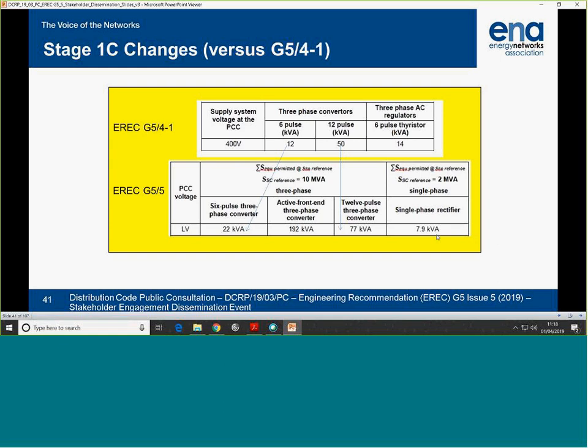And the new figures are from using a revised emission profile, different summation exponents and planning level, all these aspects. And THD is included as well, 22 kVA, so the number has gone up significantly. For the 12 pulse, it's gone from 50 to 77. For active front end converters, so that shows with modulated converters, 192 kVA. And we've also got a single-phase rectifier case shown as well.